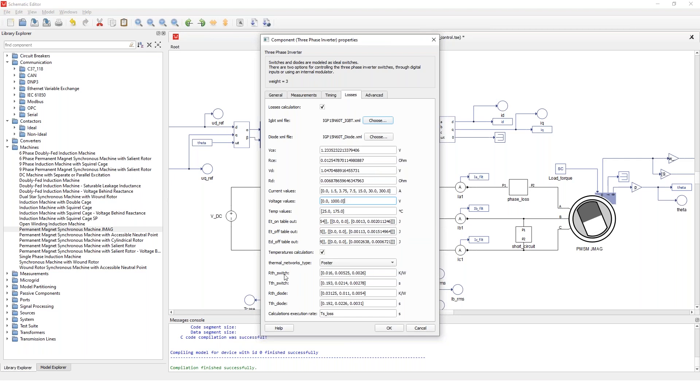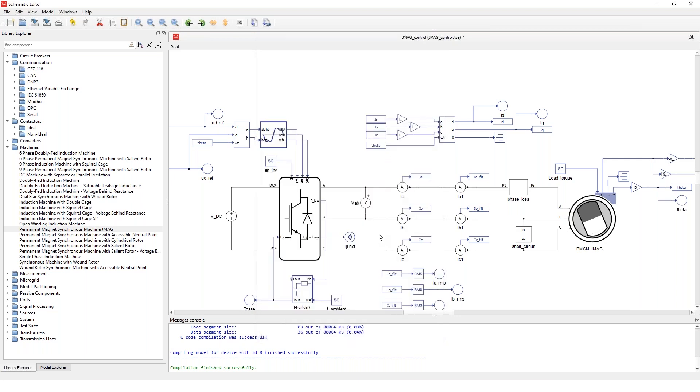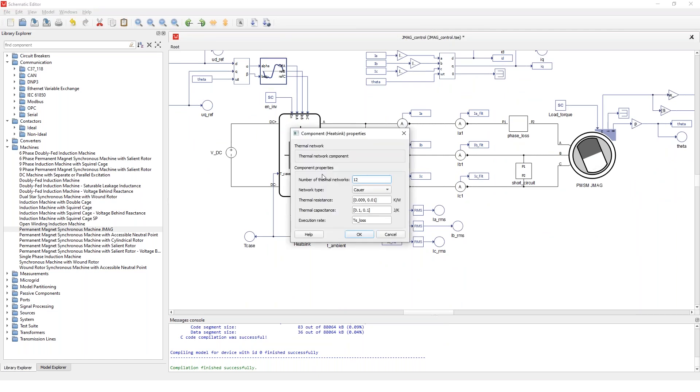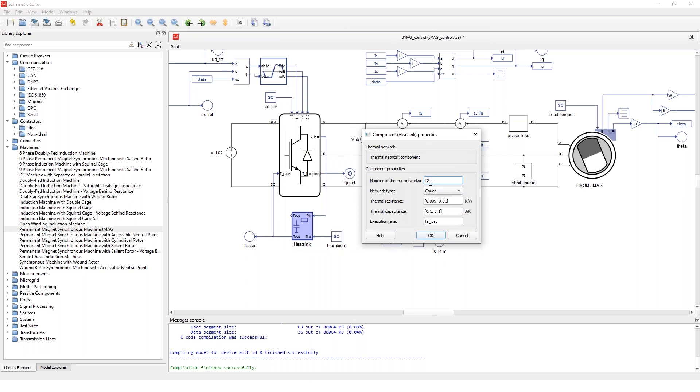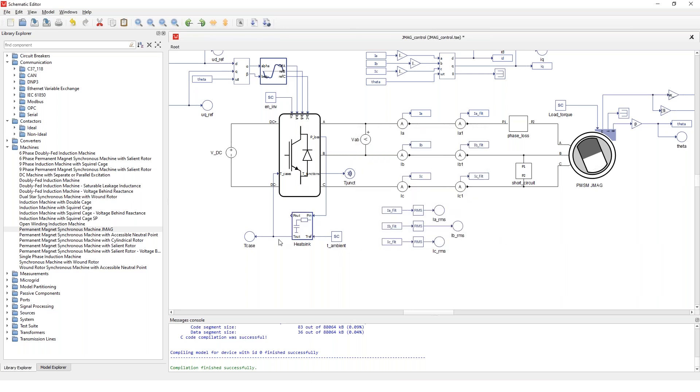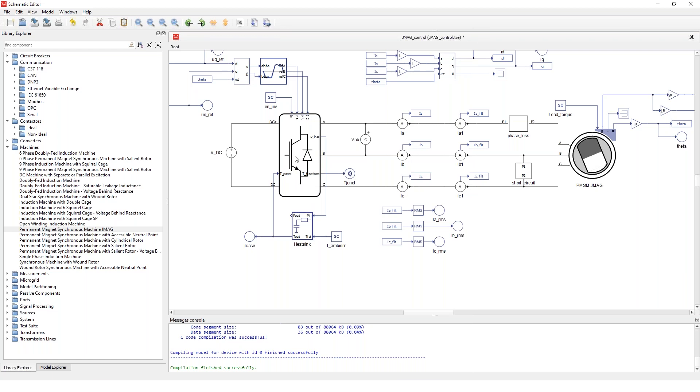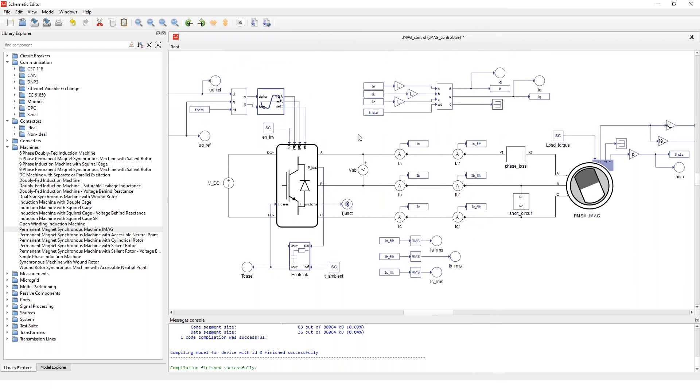Similarly, the thermal properties of the switches are simulated with these characteristics. And then on the outside, I have a thermal network component that actually simulates the heatsink for the switching modules. So for each of the switches, for each of the diodes, the IGBTs, I have one thermal network and each thermal network is represented by a two-branch Cauer model. I feed the output temperatures of the cases into the thermal model for the switches and that's how I create the loop.